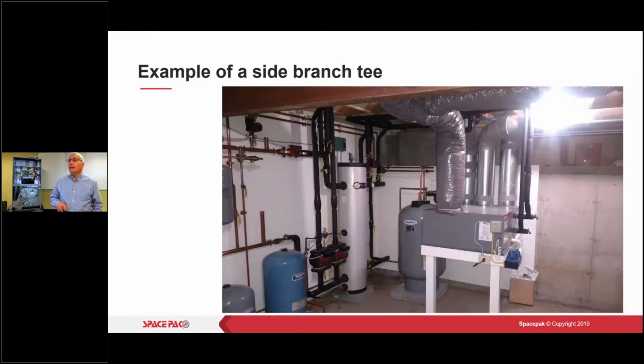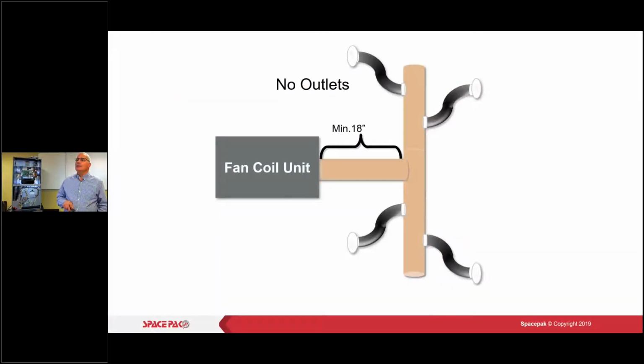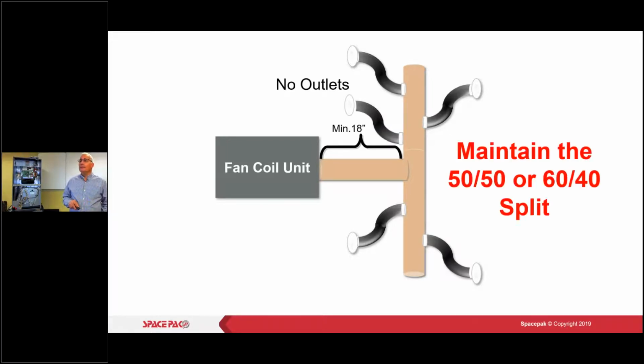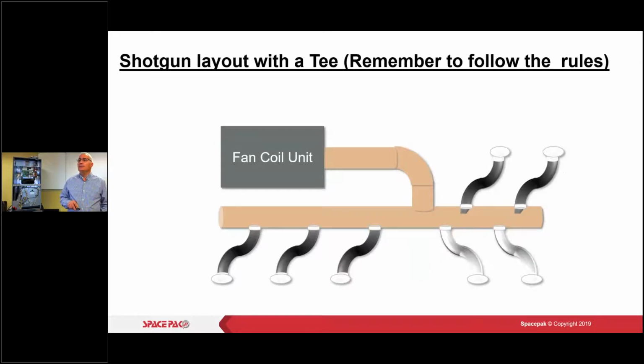All right, and in this picture here is an example of a side branch T. Again, that's a chiller system, by the way. That's a really cool, nice install. Another very popular install is this way. So again, 18 inches minimum coming off of the air handler before we hit the plenum. And we have no outlets there. And then we start to have our drops coming off, as you can see. 50-50 split is the best. 60-40 will work. Okay. That's what we want to see out in the field.